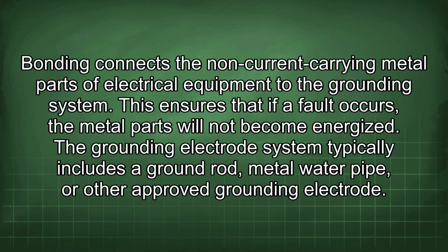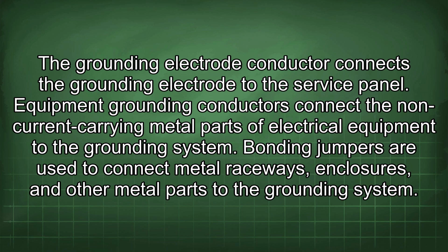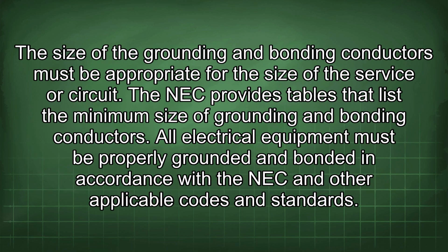The grounding electrode system typically includes a ground rod, metal water pipe, or other approved grounding electrode. The grounding electrode conductor connects the grounding electrode to the service panel. Equipment grounding conductors connect the non-current carrying metal parts of electrical equipment to the grounding system. Bonding jumpers are used to connect metal raceways, enclosures, and other metal parts to the grounding system. The size of the grounding and bonding conductors must be appropriate for the size of the service or circuit. The NEC provides tables that list the minimum size of grounding and bonding conductors.